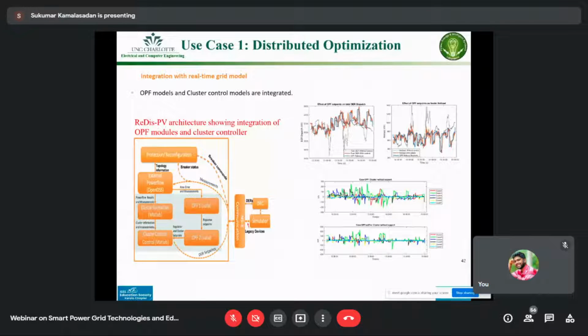So how are we managing them? We look at the distributed energy resources, PV and batteries, in the form of a group, which we call a cluster — fictitiously, meaning virtually. The real hardware in the field doesn't know it's part of the cluster, but after we make them part of the cluster, we give dispatch set points to the devices in the field, and the devices, when sending power using the dispatch set point, are able to maintain the overall objective of reducing the losses.